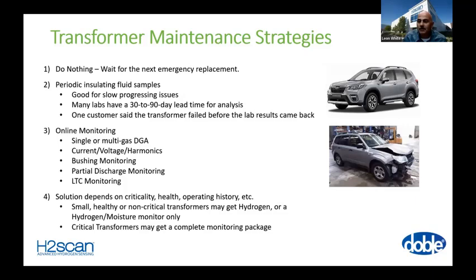what do you guys see at the Doble lab as far as typical oil sample times? It depends usually on the MVA of the transformer, and anything which is considered 10 MVA or above would usually be annual. Some places we went up to 50 MVA and higher, and they would be annual or two yearly. So it depends on the individual organization and how risk averse they are and how well they understand the oil sampling process.